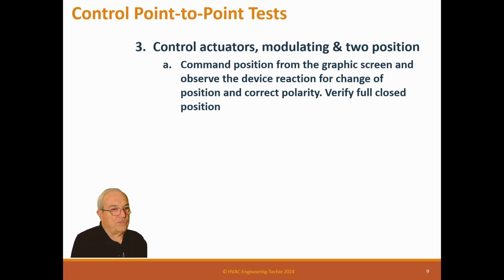Verify fully closed position. Now sometimes if you have really slow actuators like VAV boxes, VAV boxes are dumb slow, man. They drive you crazy. They could be 180 seconds. So you're standing around trying to wait for the thing. So in those conditions, we normally do these tests for a whole group of boxes at a time. So basically we'll say, okay, we got 5 boxes in this room, drive all the dampers full open. And then as they're doing that, we're actually now on one of them, and we say, okay, let's look at the hot water valve. Turn the hot water valve on. And that's a much quicker sequence, maybe 10, 15 seconds, so we'll get that done.